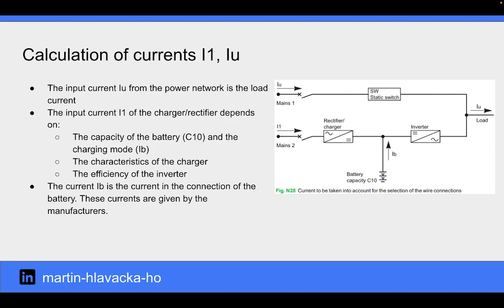The input current Iu from the power network is the load current. The input current of the charger rectifier depends on the capacity of the battery and the charging mode, the characteristics of the charger, and the efficiency of the inverter. The current IB is the current in the connection of the battery. All these currents are given by the manufacturers.